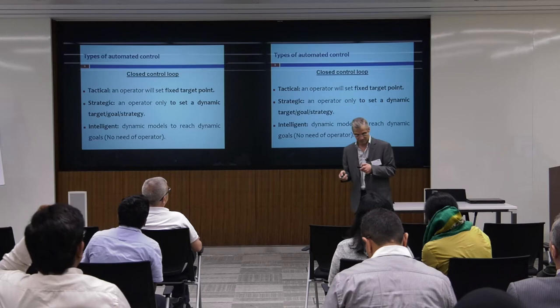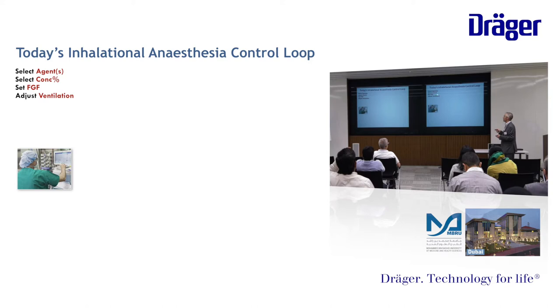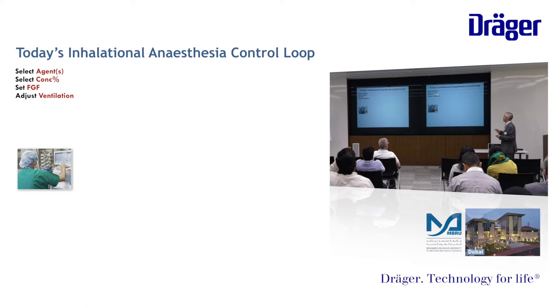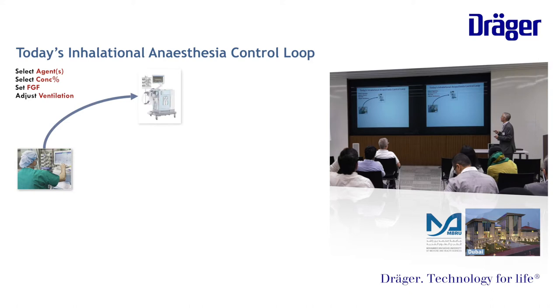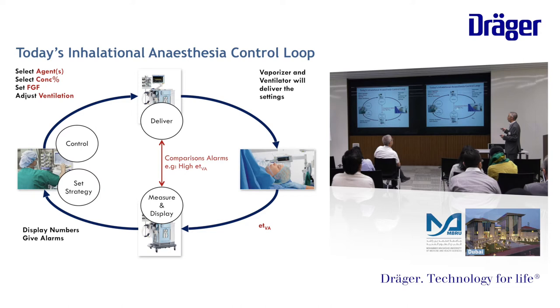Thanks God that the current machines are strategic — not intelligent. Today, in inhalation anesthesia practice, we are selecting the agent, selecting the concentration, selecting the fresh gas flow, adjusting the ventilator setting, and giving all this input to the machine. The machine drives to the patient via vaporizers. The patient gives us end-tidal volatile anesthetic displayed on the machine. The operator analyzes this output and makes a decision. He is the one controlling strategy while the machine just delivers and measures. There is no impact of output on input except through the operator — this is an open loop.